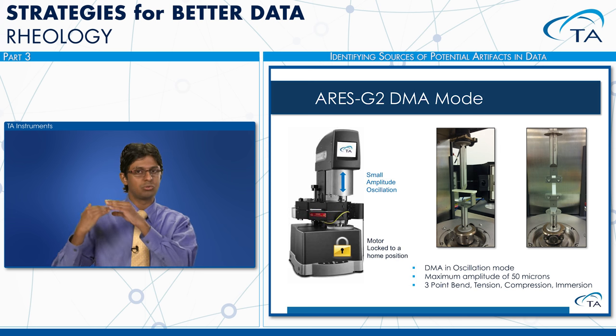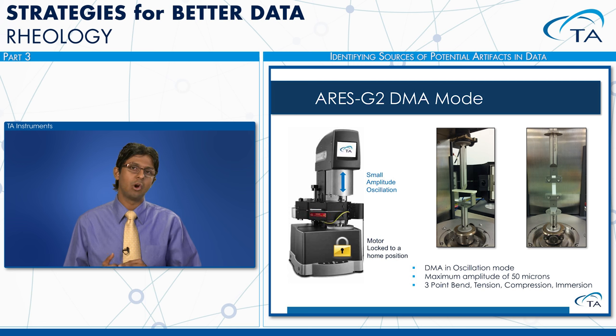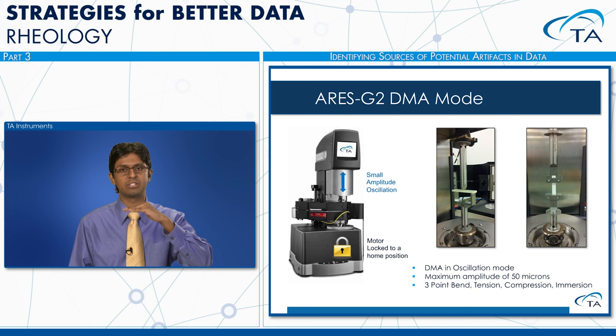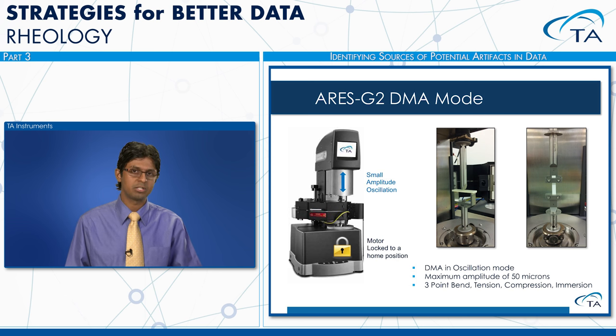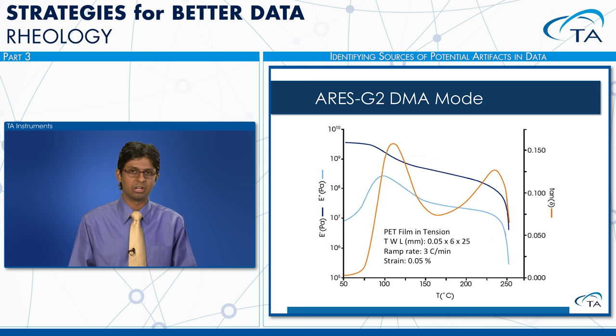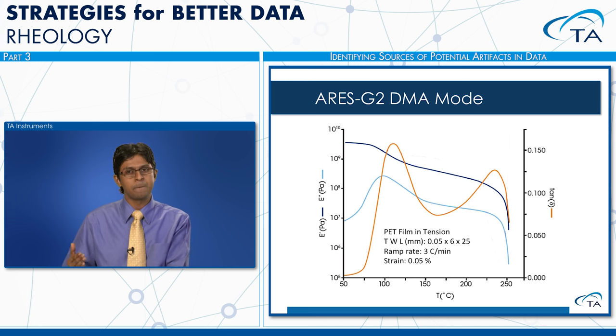Applying small amplitude axial oscillations also enables the ARES G2 to function as a DMA (dynamic mechanical analyzer) for solid materials. By locking the shear motor and actuating only the FRT transducer with up to 50 micron amplitude, solid materials can be tested in three-point bending, compression, and tension modes. A PET film tension example captures transitions evidenced by peaks in tan delta — material property measurements previously requiring a separate instrument like the RSA G2 or DMA Q800.